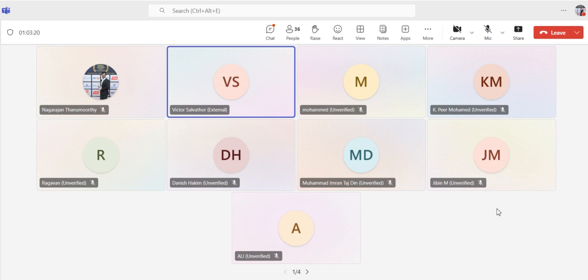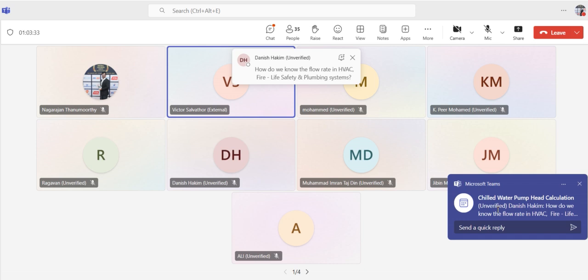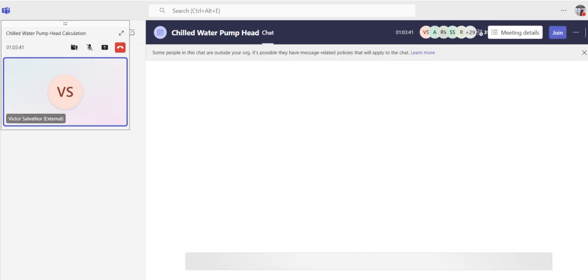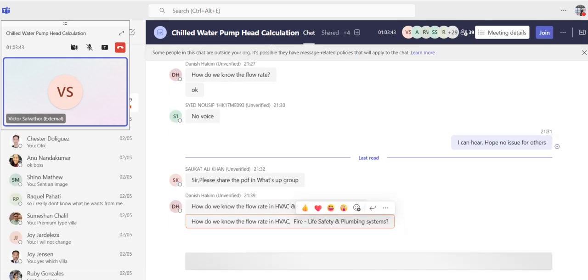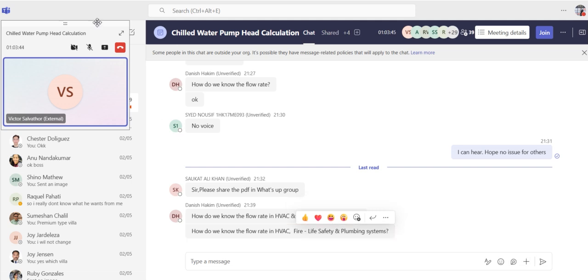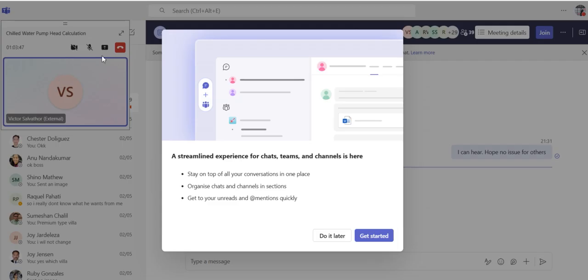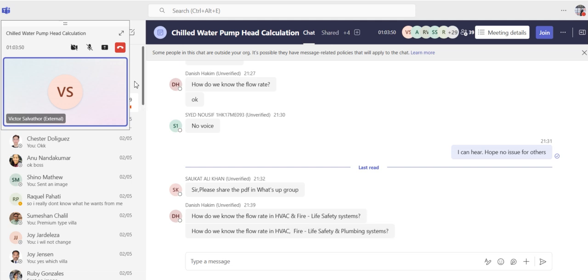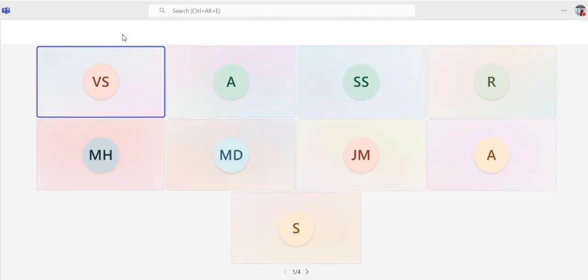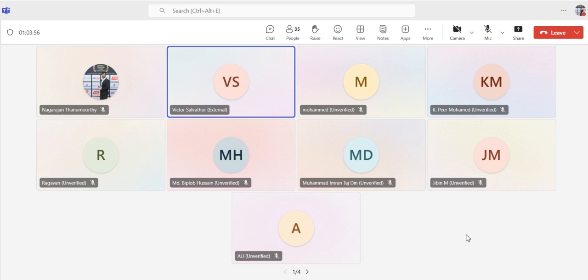Okay. So why did I not consider the static head here? Usually this applies when you go for a closed system. Here we are doing the pump head calculation because the system is already pressurized. We are doing the pressurized system calculation, not the chilled water system calculation. When you do this pump head calculation, it's considered a pressurized system. So why are we not considering the static head here? I will explain a little more on that.